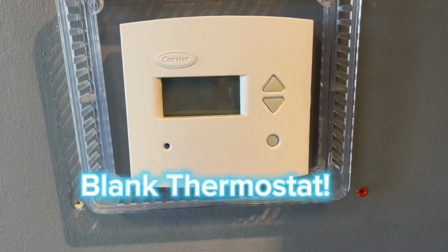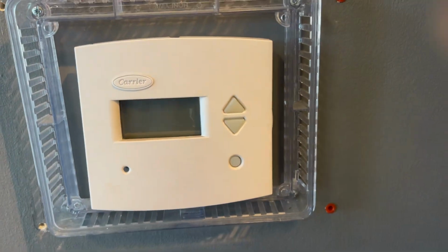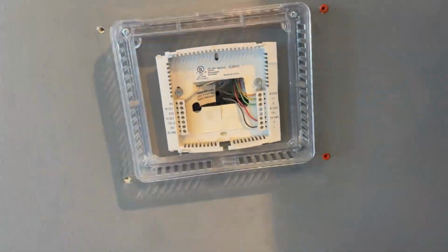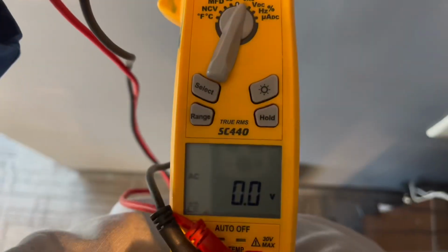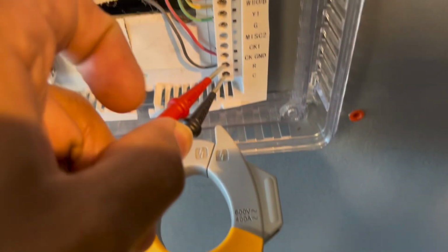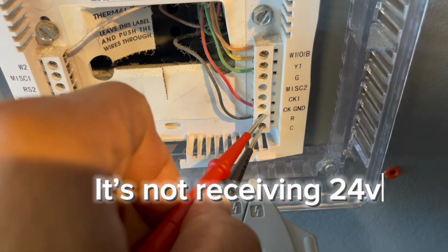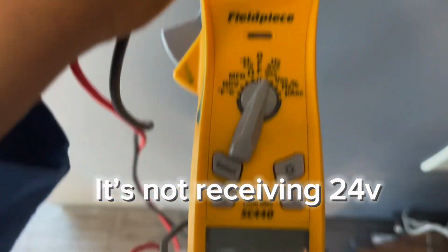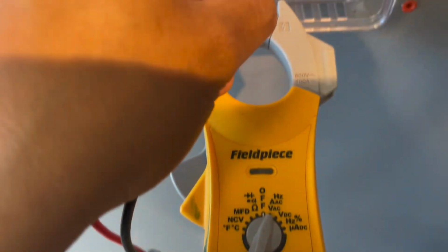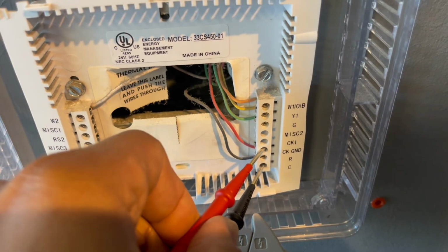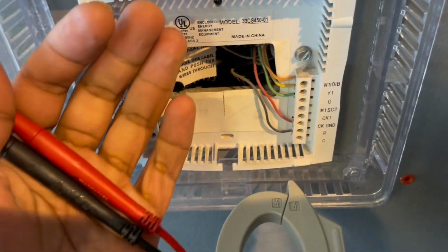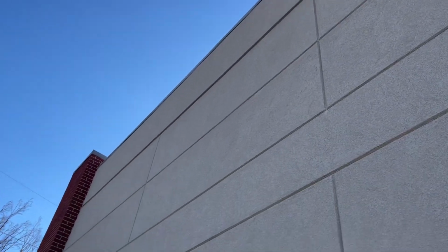Alright, so the first thing that we notice right here is that the thermostat is blank. There is nothing showing at this moment. So we're going to remove the cover and check the 24 volts, and we're not receiving voltage. So it means that we have to go to the roof and check the RTU and see what's going on with the transformer. Let's go. So now we have to go all the way up there to check the RTU. Let's see.